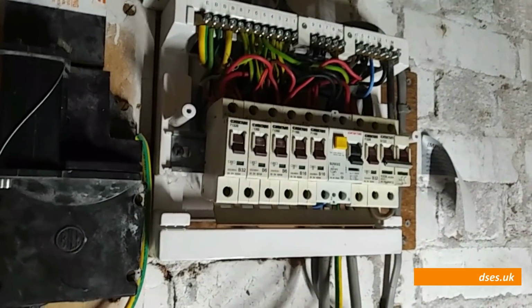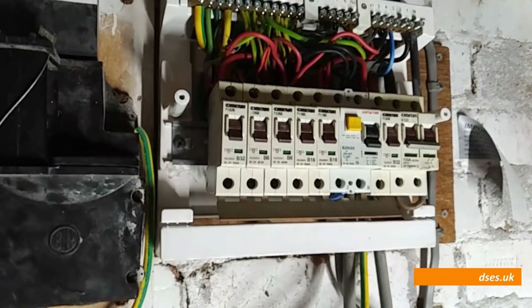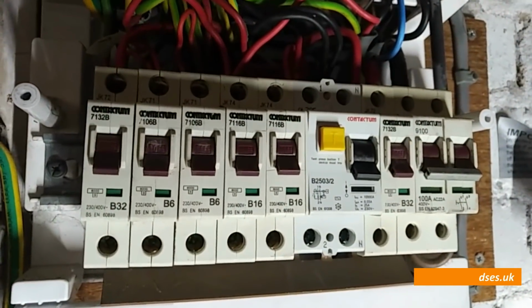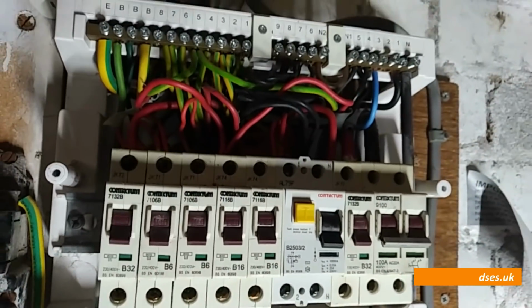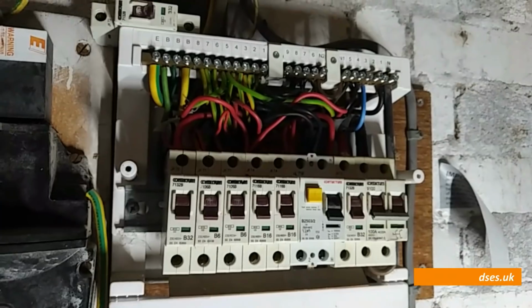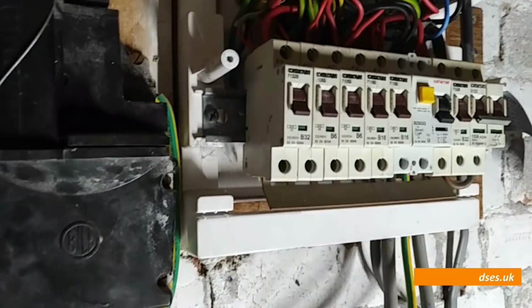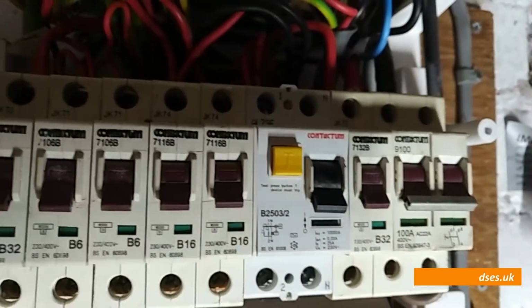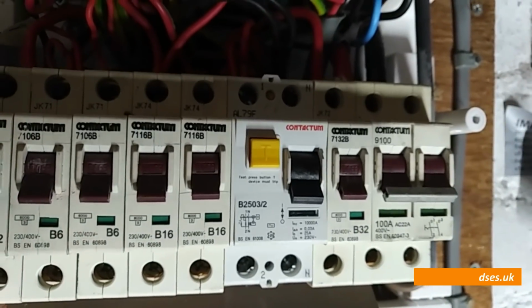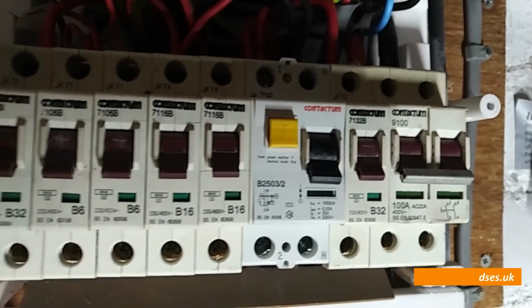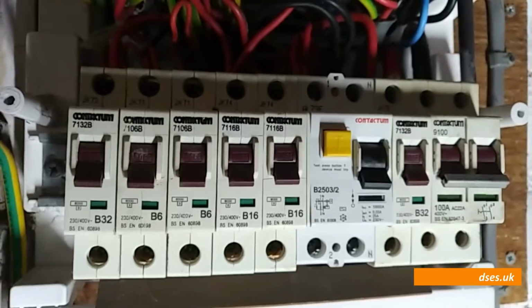So I'm going to have to replace that with an actual RCBO in order to give them the overcurrent and the earth leakage protection. I'm going to have to source one still at 25 amps because I think, you know, they're kind of right on that front.